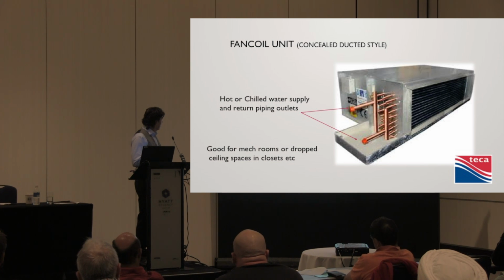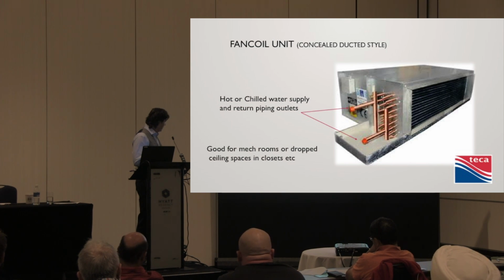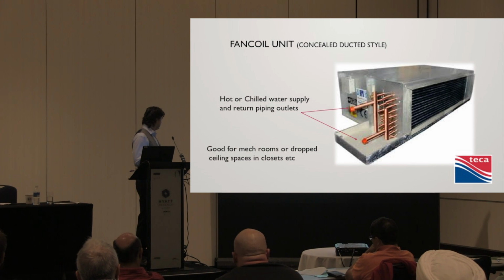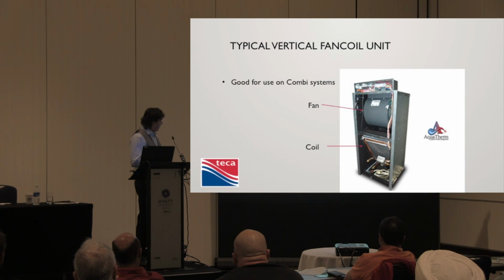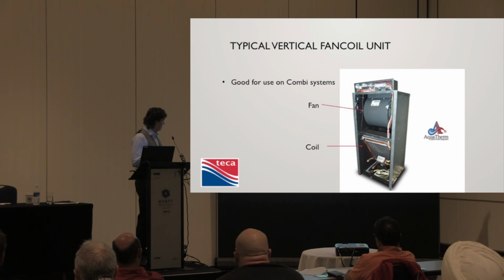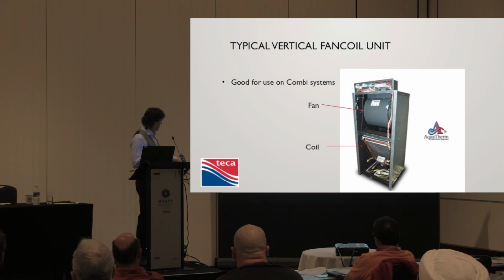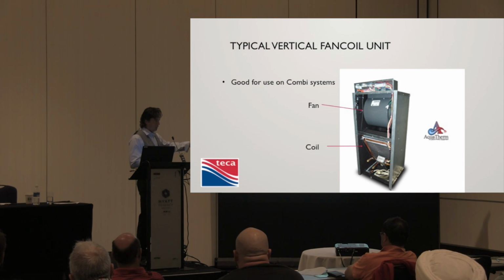So these guys here, hot and chilled water, whatever you want to use in there. You see it's got a condensate pan right there, so you just pipe it into your hydronics. These things you put in closets, or this is a rather large one. They make them as shallow as about 9 inches thick. So if you wanted to put it in, say, a master bedroom closet, drop the ceiling, something like that, you could do that. Or in a mechanical room, however. You see these probably most often. It just looks like a household furnace, but there's your hot water coil down there and your fan up there. Pretty simple idea. Again, you often see that standing beside a boiler or a combi boiler.